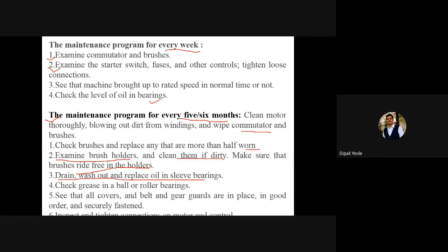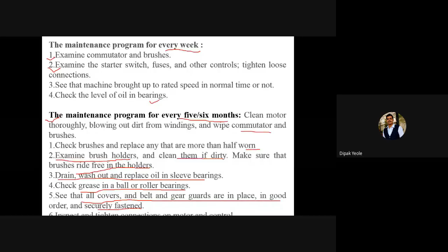Drain or wash out and replace oil in sleeve bearings. Check the grease in ball or roller bearings. See that all the covers and belt and gear guards are in place, in good order and securely fastened. Inspect and tighten the connections on motor and control. So this is the maintenance program for half yearly and every week, and next is the one for every year.